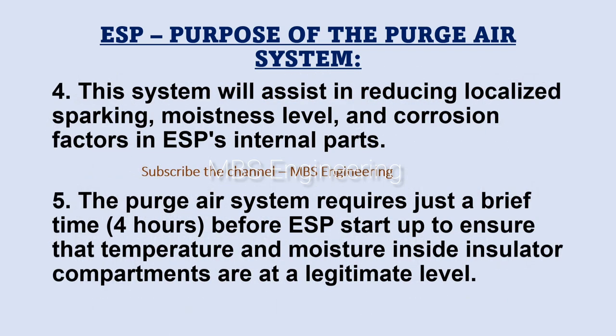Point four: this system will assist in reducing localized sparking, moistness level, and corrosion factors in the ESP's internal parts. Point five: the purge air system requires just a brief time — four hours — before ESP startup, to ensure that temperature and moisture inside insulator compartments are at a legitimate level.